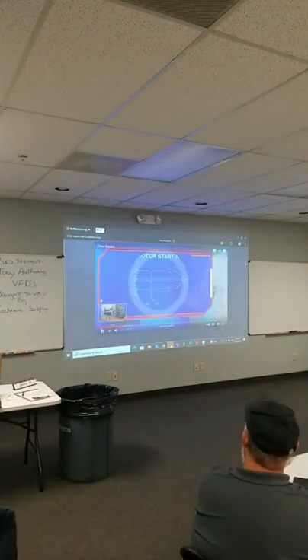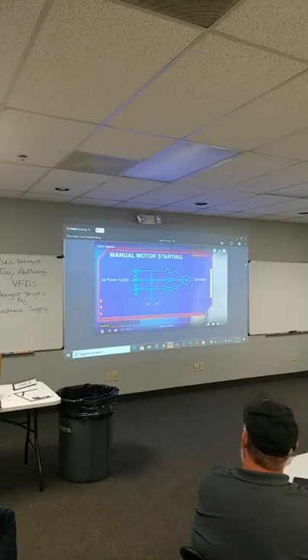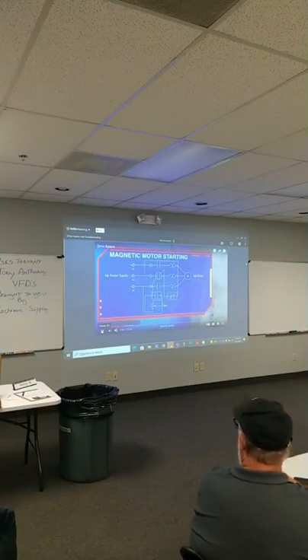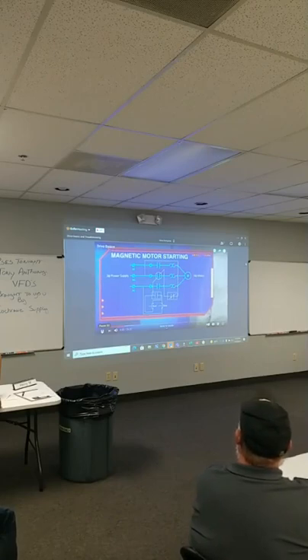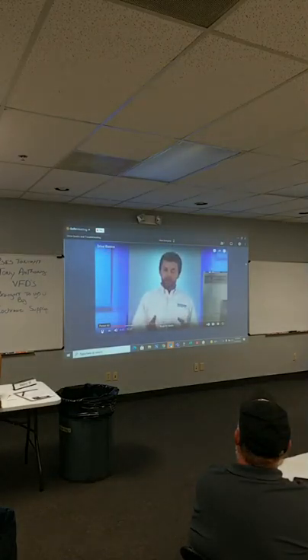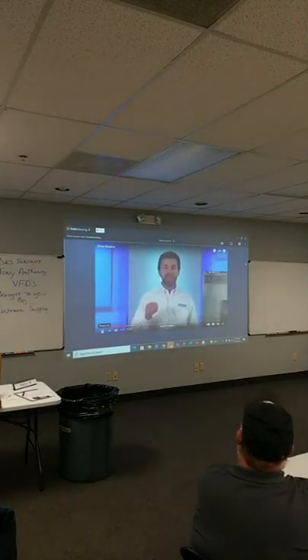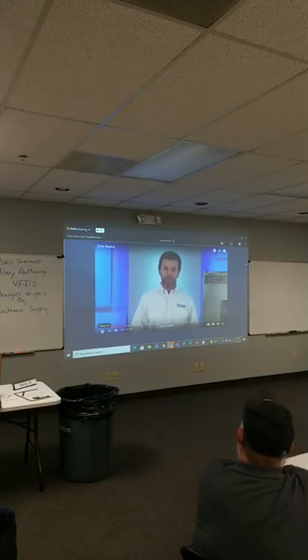The simplest form of control is a manual motor starter, which is nothing more than a means to manually open and close the contacts to start and stop the motor. Manual motor starters usually include some type of motor overload protection. A magnetic motor starter is similar to a manual starter, except you can remotely toggle a magnetic coil to bring in contacts as needed. A drawback for both manual and magnetic motor starters is that they do not reduce the inrush current that the system will experience at startup.